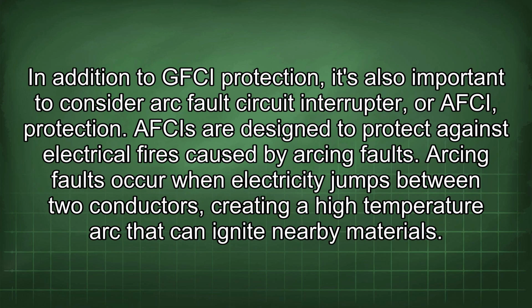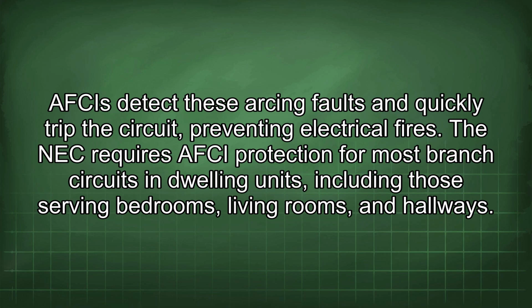In addition to GFCI protection, it's also important to consider arc fault circuit interrupter, or AFCI, protection. AFCIs are designed to protect against electrical fires caused by arcing faults. Arcing faults occur when electricity jumps between two conductors, creating a high-temperature arc that can ignite nearby materials. AFCIs detect these arcing faults and quickly trip the circuit, preventing electrical fires. The NEC requires AFCI protection for most branch circuits in dwelling units, including those serving bedrooms, living rooms, and hallways.